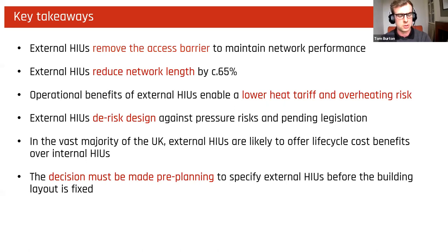This is a very good way of de-risking your design against both pressure risks by removing that high pressure pipework from dwellings, and also against pending legislation, so the BC and the heat network market framework coming through. And as you saw in the two graphs just now, apart from in the most expensive areas in the country, in a vast majority of the country, external HIUs are likely to offer life cycle cost benefits over internal HIUs. But if this is something that you're considering or would like to include on future projects, the decision needs to be made pre-planning and as early as possible to specify external HIUs before the building layout is fixed.